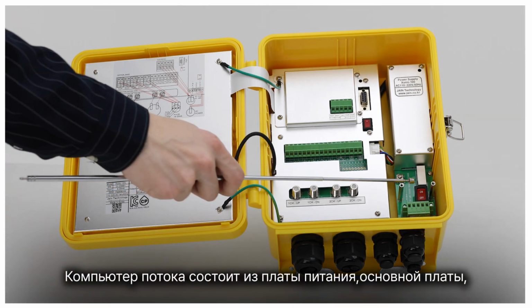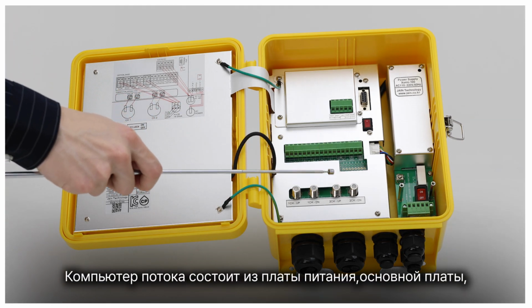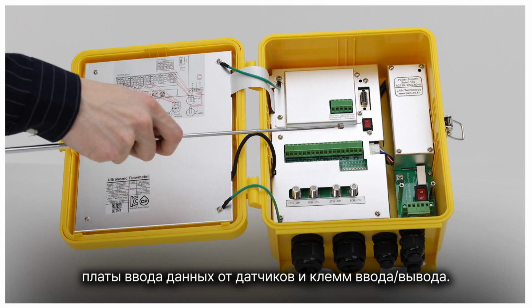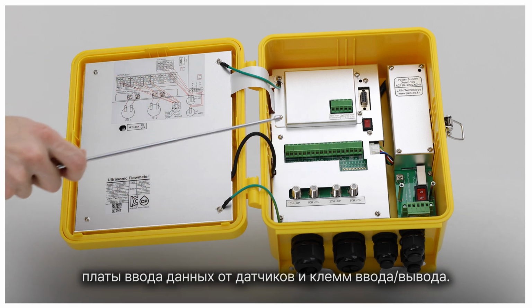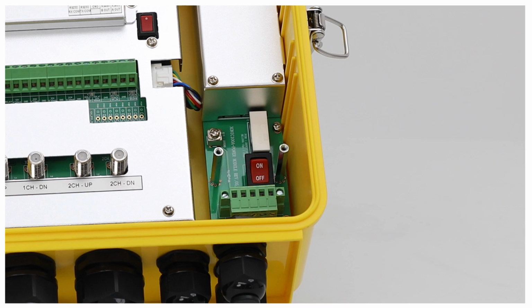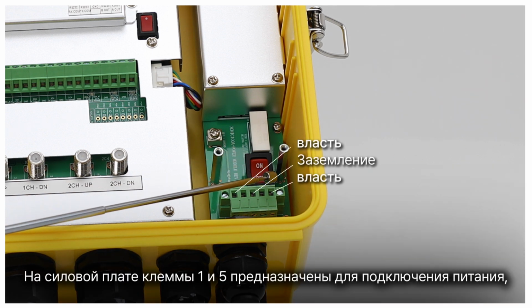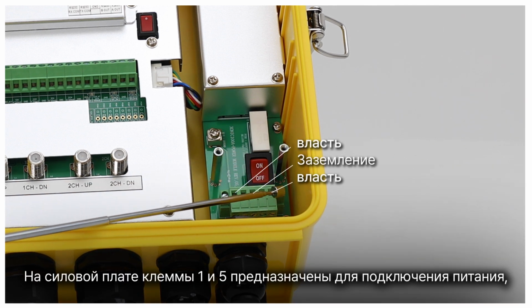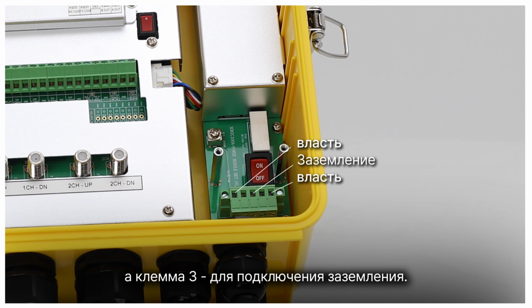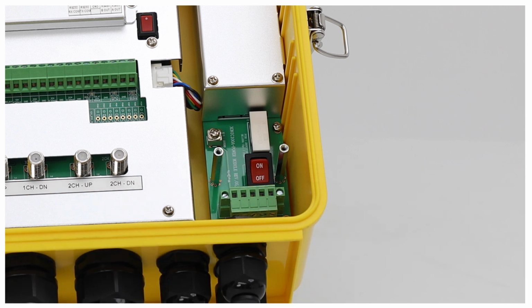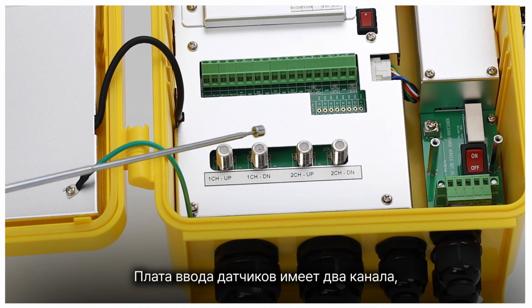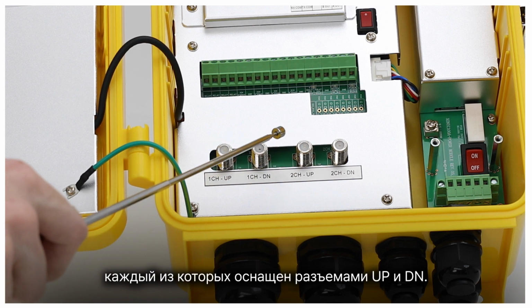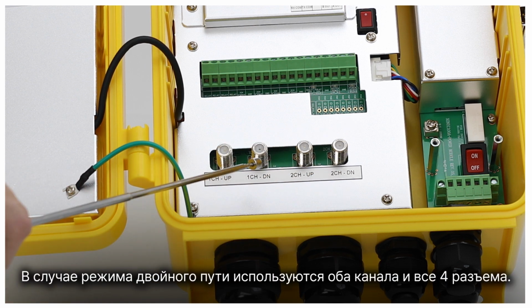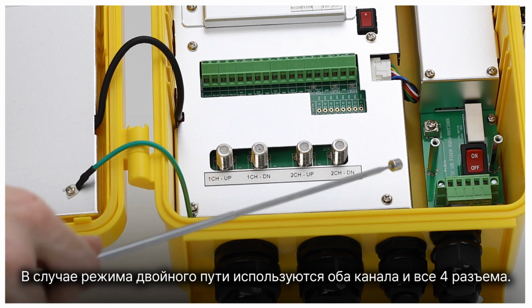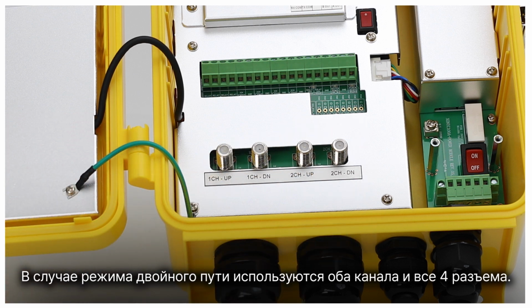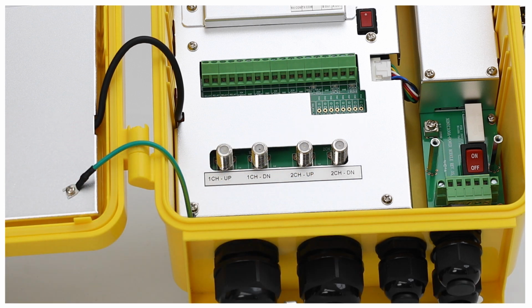The flow computer consists of a power board, a main board, a sensor input board, and input-output terminals. On the power board, terminals 1 and 5 are for power, and terminal 3 is for ground connection. The sensor input board has two channels, and each channel has up and down connectors. In the case of dual path mode, both channels and all four connectors are used.